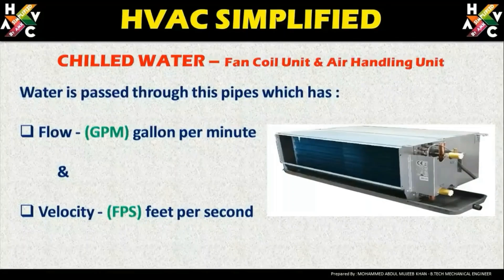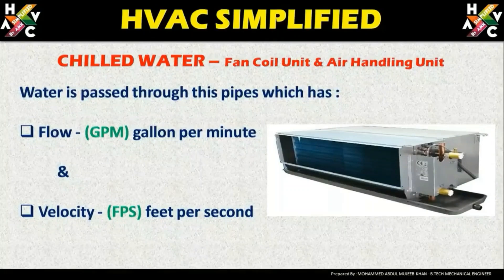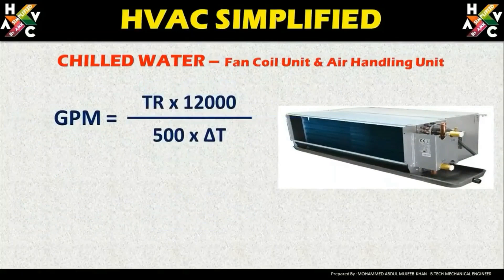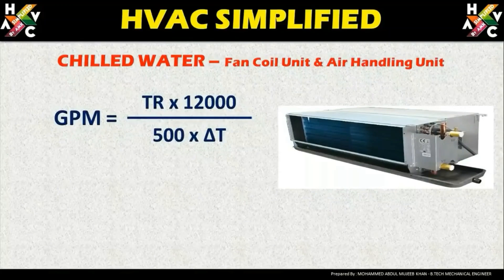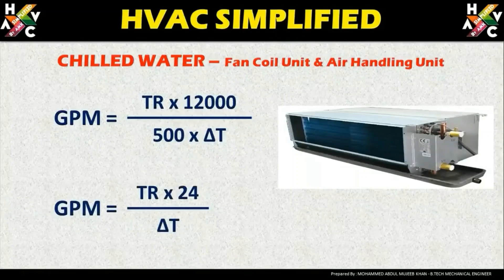For any fan coil unit, these are the two basic parameters we need to understand: GPM and FPS, which is also known as feet per second. Now let us understand the formula for GPM. GPM is equal to TR multiplied by 12,000, divided by 500 multiplied by delta T, which is further simplified to TR multiplied by 24 divided by delta T.